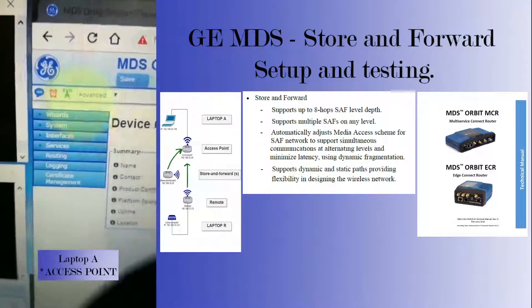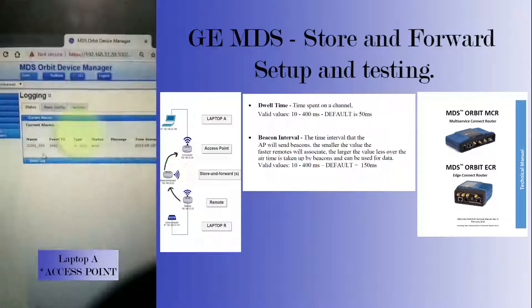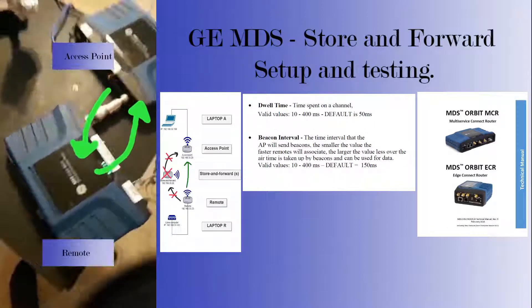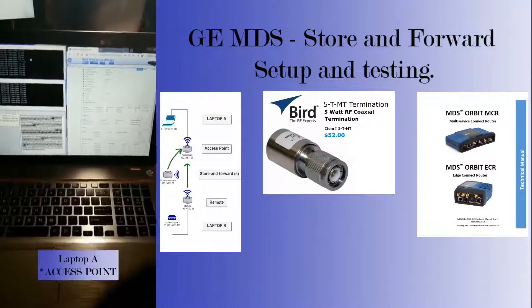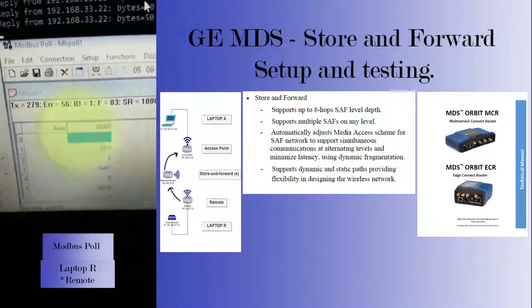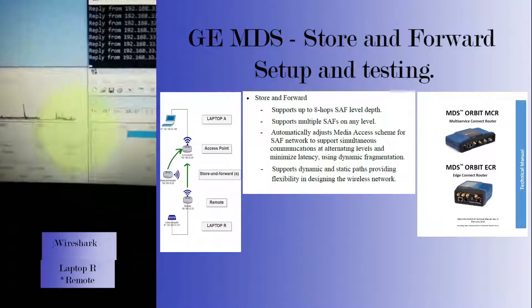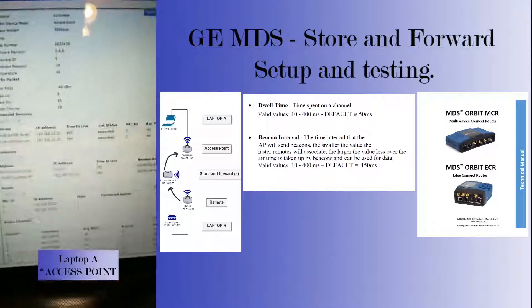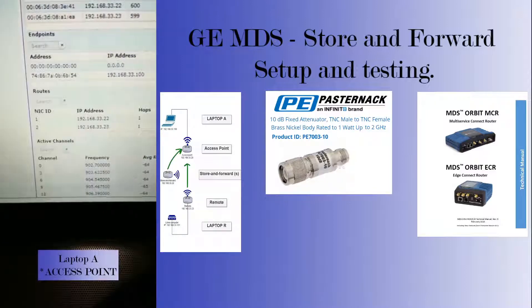Back at the access point — we're talking, everything's still working, data's back flowing. If you look at the errors, we've had very little — started with 12, about doubled since. We now see our remote and store-and-forward are back online. We've got an alarm icon that's red on our page. If we click on it, it takes us to our current log where the alarm is showing, and we hit the clear button. Traffic is flowing again, we're pinging, and we can see our remote and store-and-forward both associated at one hop — both communicating directly.